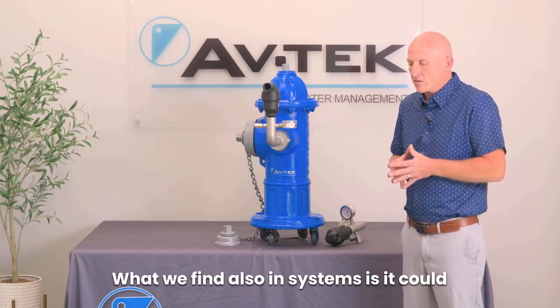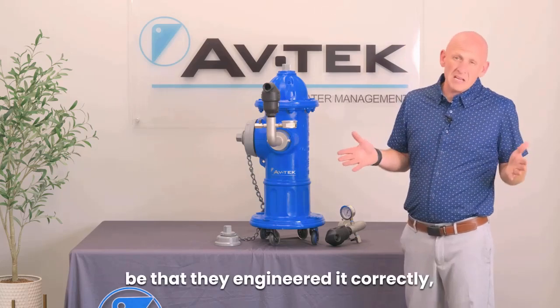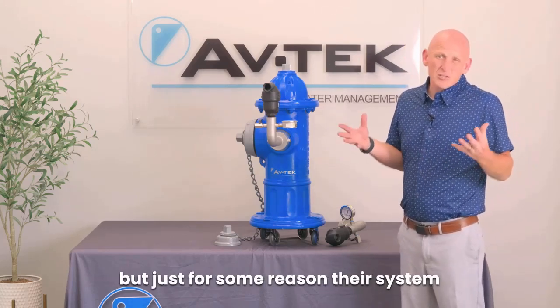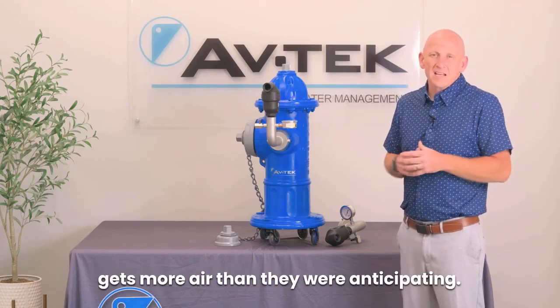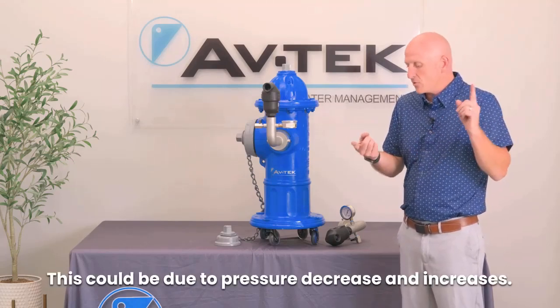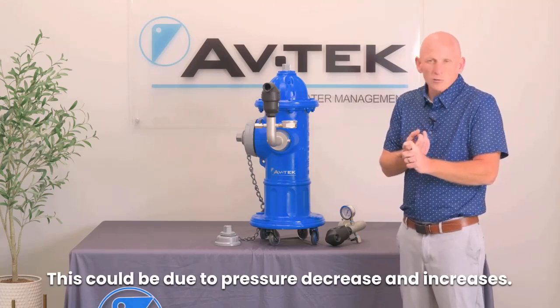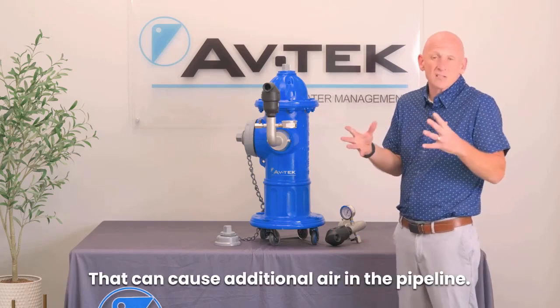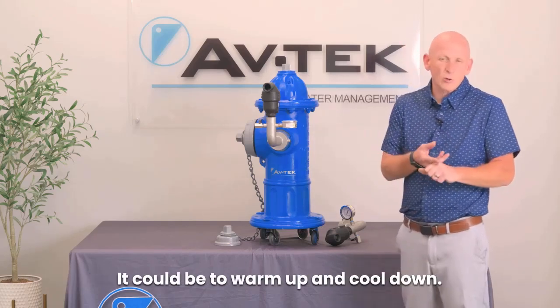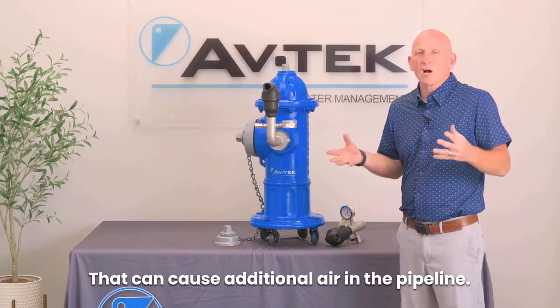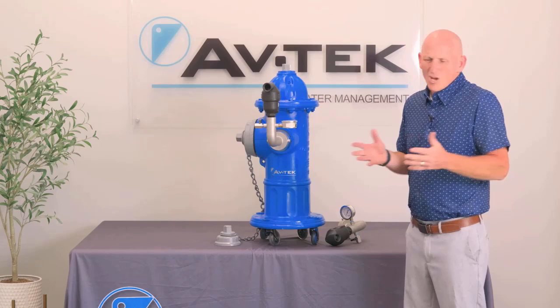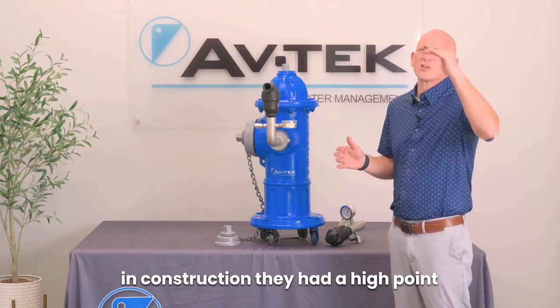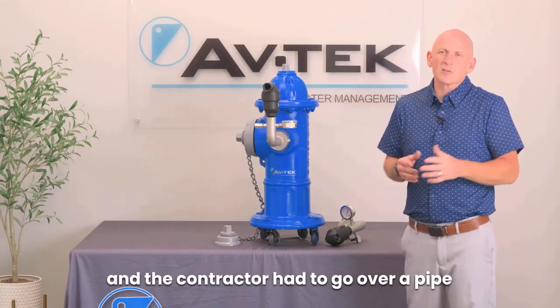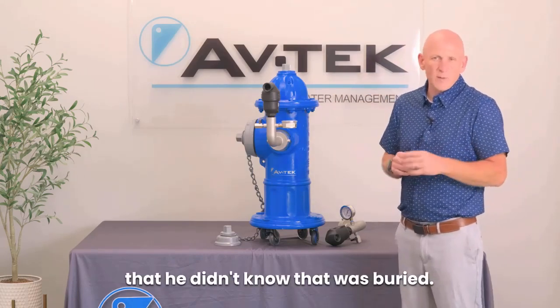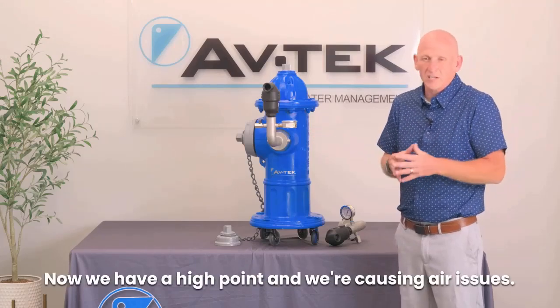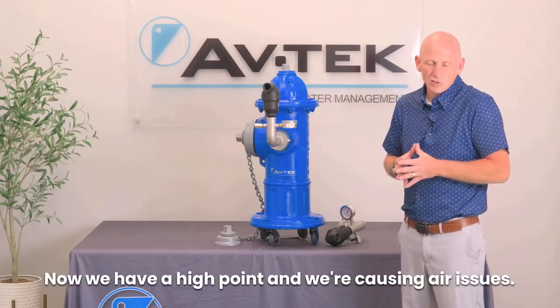What we find also in systems is it could be that they engineered it correctly, but for some reason their system gets more air than they were anticipating. This could be due to pressure decreases and increases. That can cause additional air in the pipeline. It could be warm up and cool down. That can cause additional air in the pipeline. Could just be that they didn't realize in construction they had a high point and the contractor had to go over a pipe that he didn't know was buried, and so they had to make an adjustment. Now we have a high point and we're causing air issues.